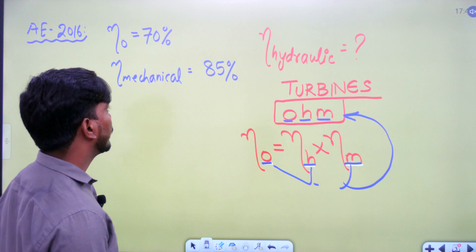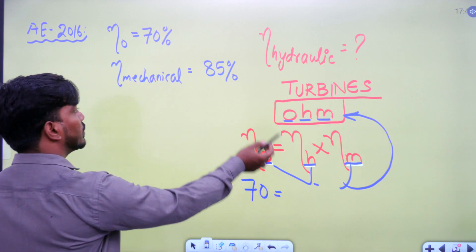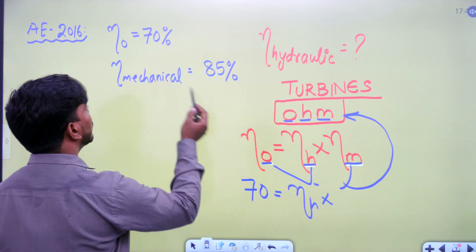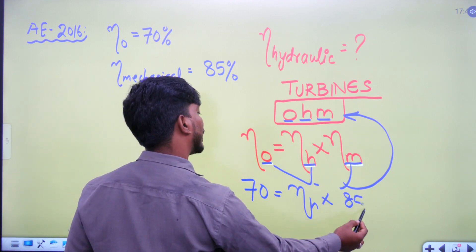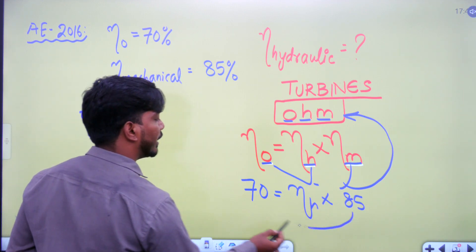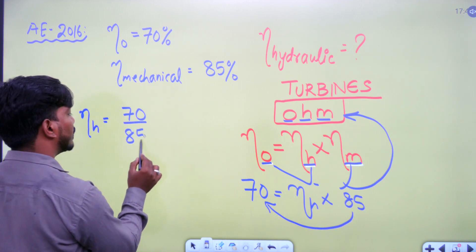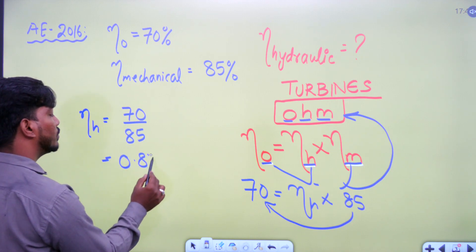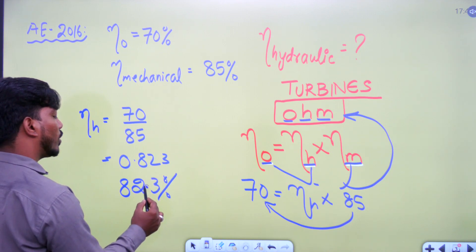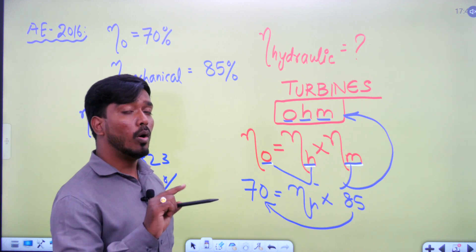For example, if overall efficiency is 70% and mechanical efficiency is 85%, then hydraulic efficiency equals 70 divided by 85, which gives approximately 0.823, or about 82.3%. You can verify based on the answer options. This type of question is easy to solve when you remember the OHM relationship.